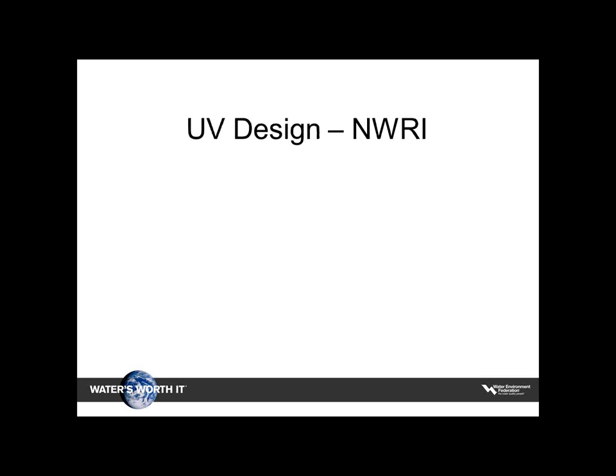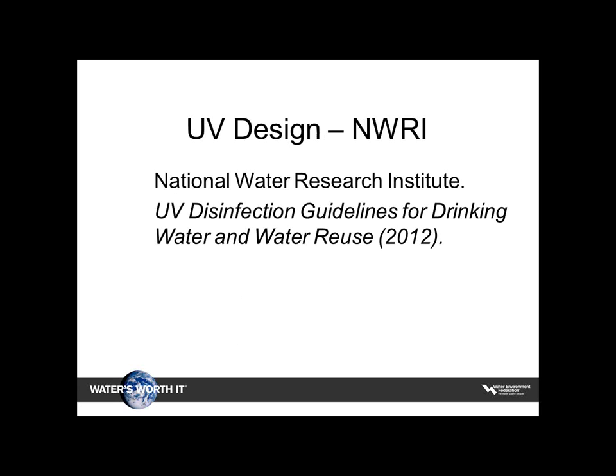And let's talk about the reuse ones from the National Water Research Institute. Again, the book's out there. It has UV disinfection guidelines for drinking water and water reuse. The reason I brought this one up is this is the one we're now falling back on for anybody that comes in with a water reuse project with us. So what are they looking at? They're looking at what type of filtration you're running through and base the doses against that.